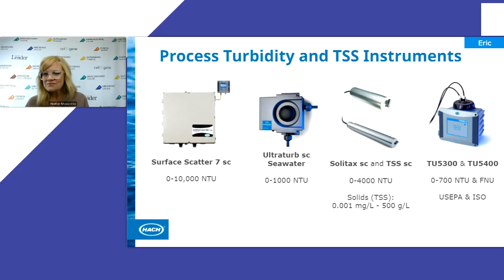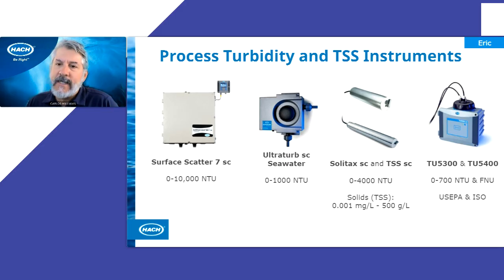Yeah, I can help with that. So really, the FNU and the NTU are a little bit of, as we say in English, tomato. In terms of the measurement and what kind of standards you would use, you could use the same thing. So if you have a turbidity standard that says it's 20 nephelometric turbidity units, that will also correlate to 20 formazin nephelometric units. The only reason that we have that is because of the different light sources. And so when we're using standards, it doesn't really matter because it's just measuring light scatter.